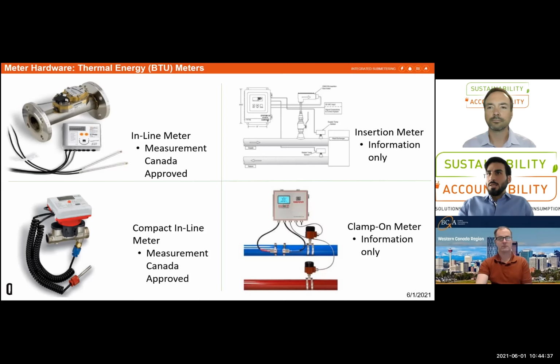Typical sizes are between 1/2 inch and 3/4 inch. Insertion type meters, one of the most popular ones that are currently used are the Onicon ones, which, depending on whether they're using a turbine type or impeller type insertion flow meter or a magnetic type flow meter, range anywhere between about $3,500 to about $6,000. And clamp-on thermal meters, depending on the manufacturer, for a complete package, including temperature sensors and clamp-on ultrasonic sensors, cost anywhere starting from about $4,500 to about $10,000.